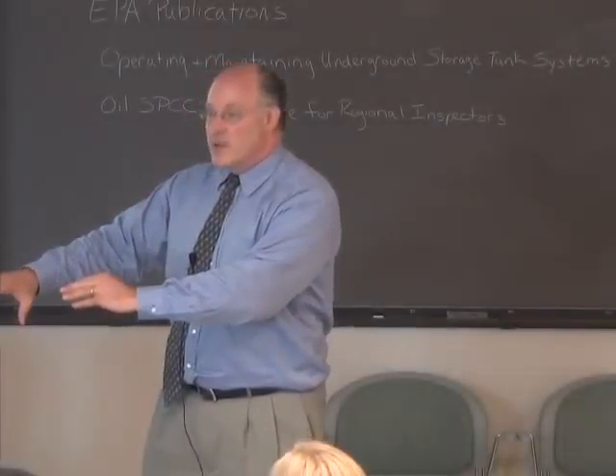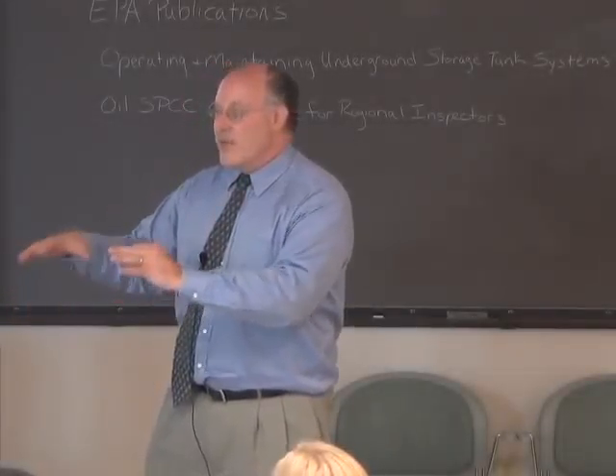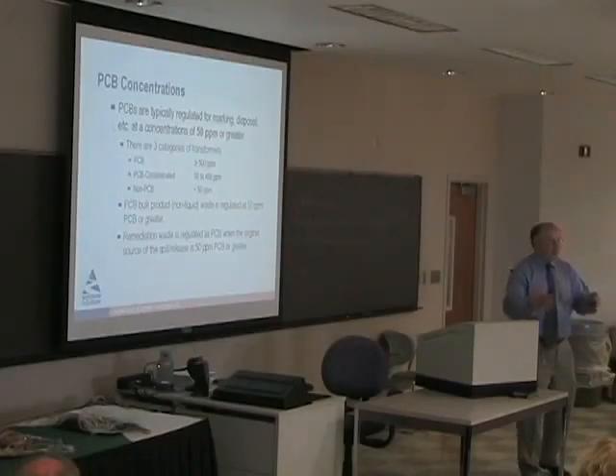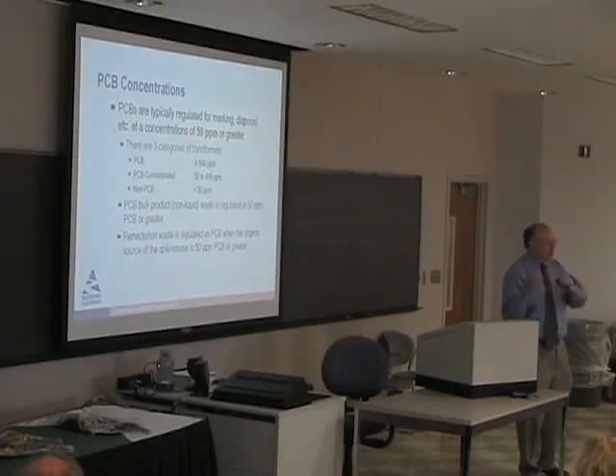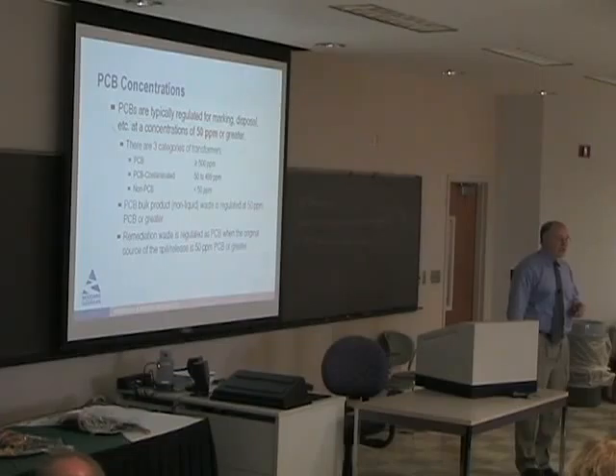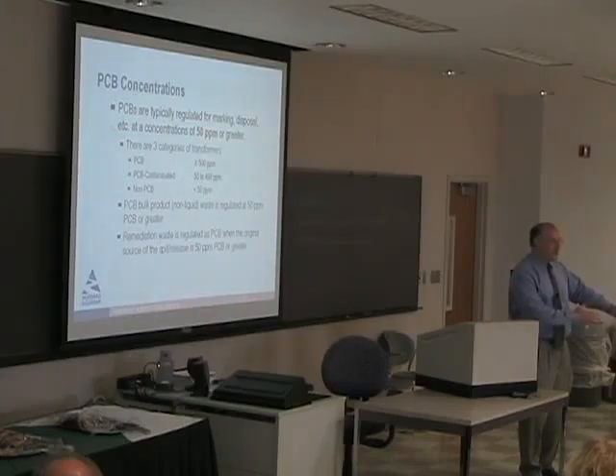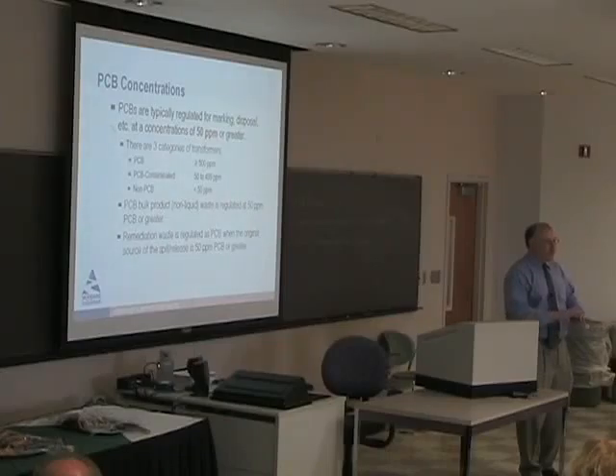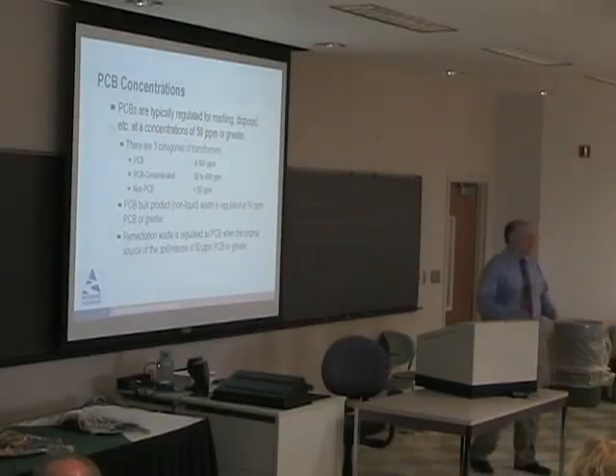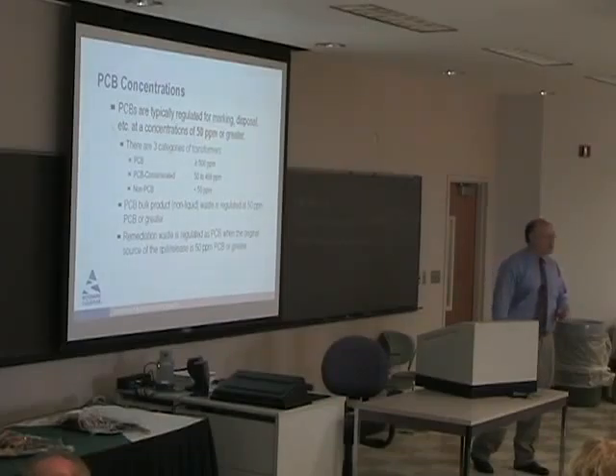Anytime it's less than 50 parts per million, we don't worry about it. The fact that it's a transformer is not important in the sense of what the regulations call for. They're only concerned with transformers that are above 50 parts per million, and in particular, transformers that are above 500 parts per million. If you have a transformer or a capacitor or a light ballast, and it's less than 50 parts per million PCBs, you don't have to worry about the regulations at all. It's not a risk. It doesn't pose an issue. There's no requirement to do anything. It's only when you're above those thresholds that you have to start thinking about it.